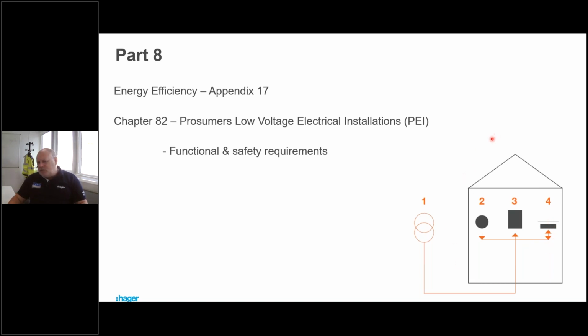For instance, if the sun is out, okay, we're producing electricity on these solar panels. The batteries could be fully charged. Do we really need this grid supply? Possibly not. We could put this installation into what they call island mode. Okay, we can do that, but what's it say here? It says functional and safety requirements have got to be adhered to. So we've got to ensure that if we do put this installation here into island mode, when we disconnect from the grid, we don't disconnect from any of the earthing arrangements that we need for this installation. Okay, that's very, very important.